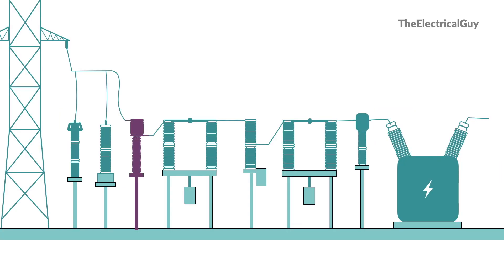One point to note here is that it is not necessary that all substations will have wave traps. Only where power line carrier communication, also called PLCC, is used will wave traps come into picture — otherwise not.